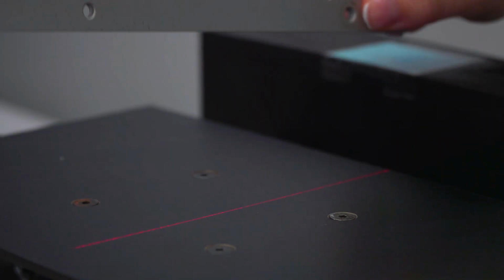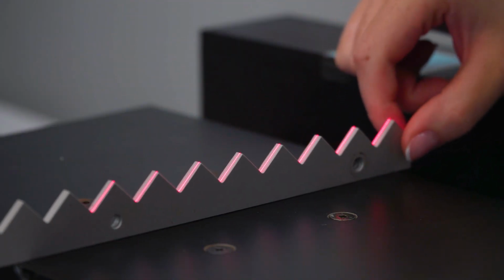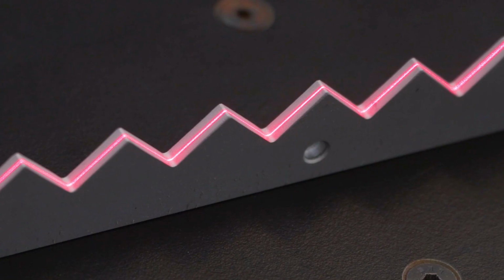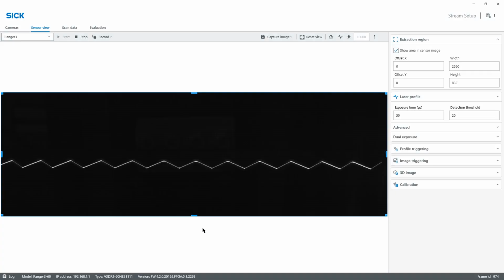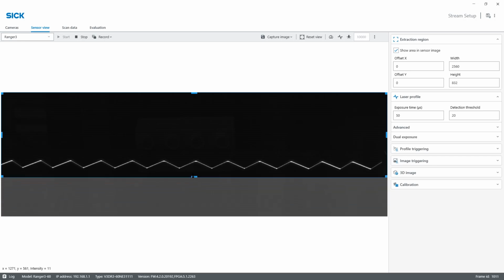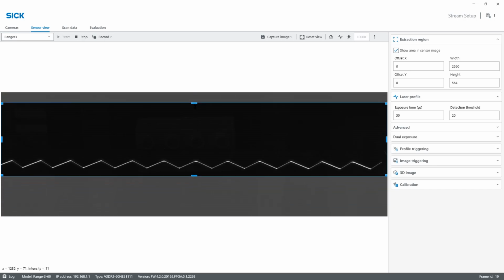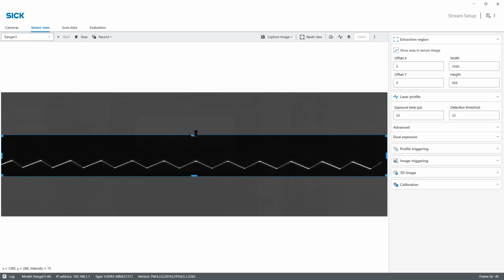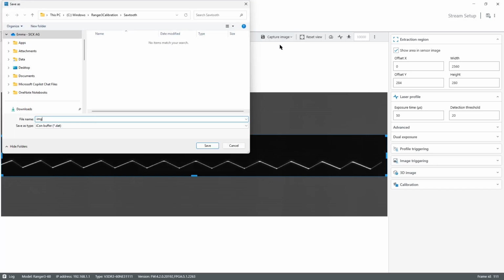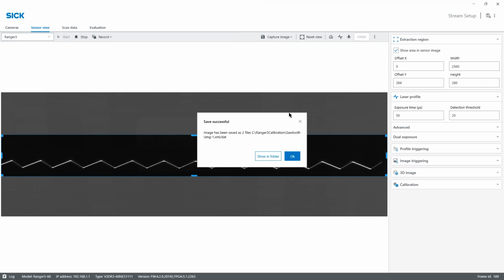To begin, place the target under the laser line and make sure that the target is properly aligned with the laser plane. In Stream Setup, head to the sensor view and ensure that the region of interest covers the peaks and valleys of the laser line. Capture a few sensor images with the target in different positions within the region of interest and save the images to a folder.